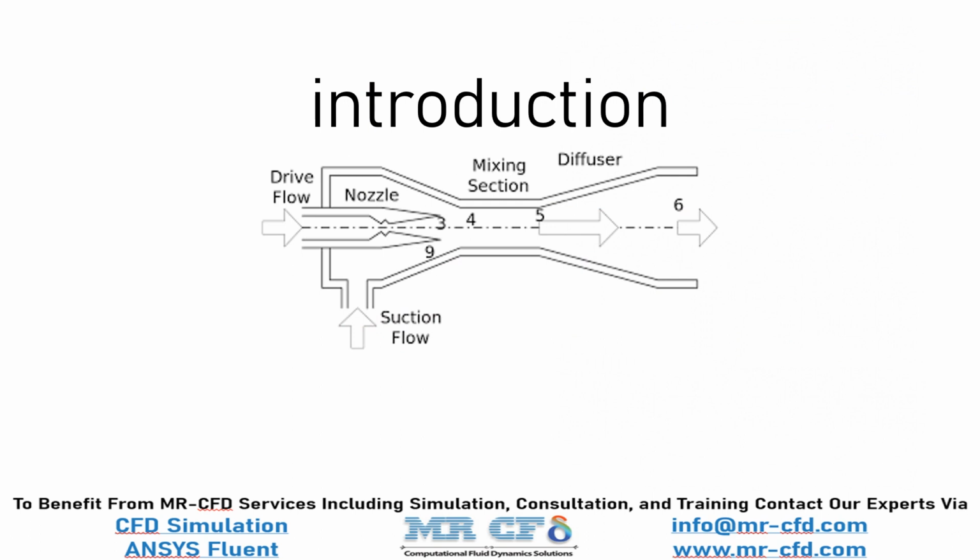In general, an ejector is a system of ducting and nozzles used to direct the flow of high-pressure fluid in such a way that the lower pressure fluid is entrained in the jet and carried through a duct to the region of high pressure. It is a fluid dynamic pump with no moving parts, excepting a valve to control the inlet flow. A steam injector is a typical application of the principle used to deliver cold water to a boiler against its pressure, using its own live or exhaust steam, replacing any mechanical pump.